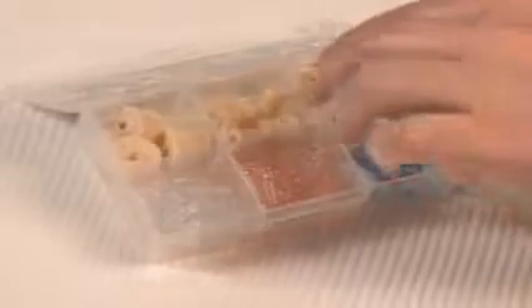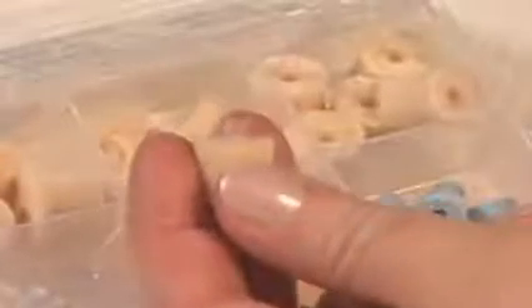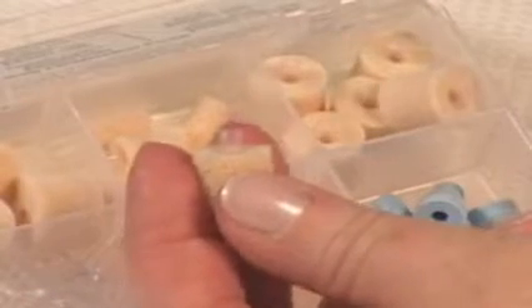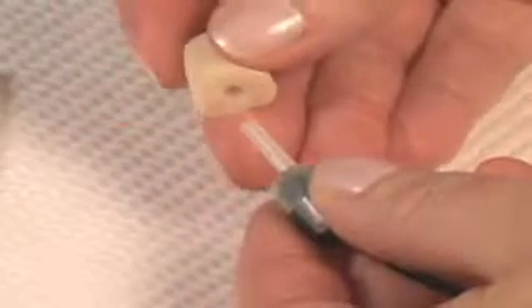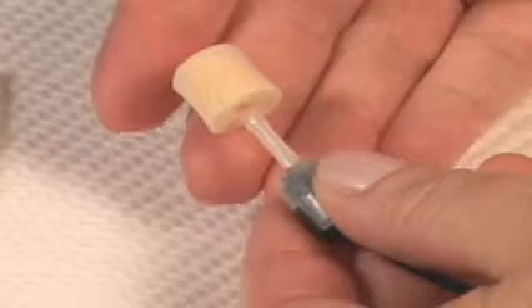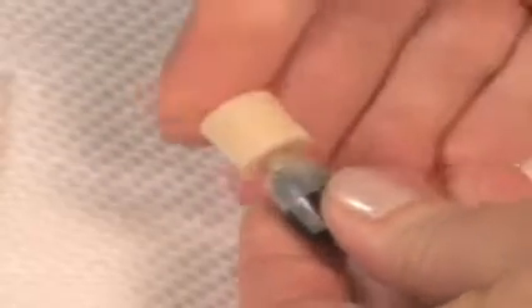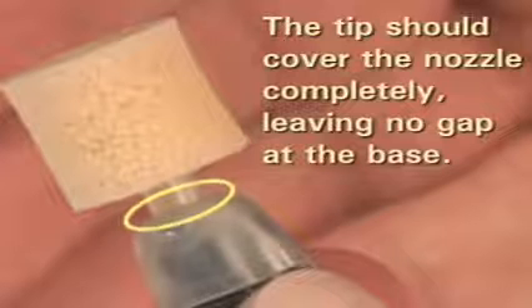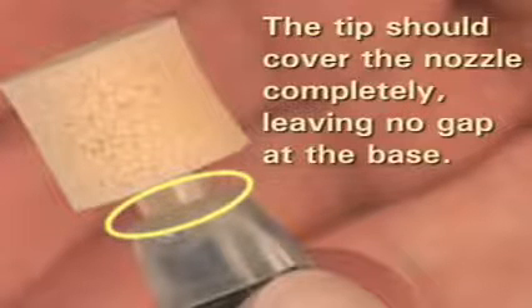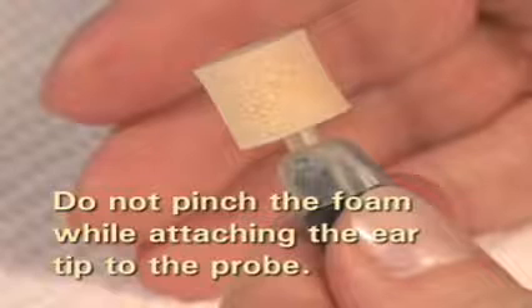For testing an older child or adult, use the beige foam ear tips. Select an ear tip that is a little larger than the patient's ear canal. Place the clear tube slightly onto the nozzle of the probe body. Then, using your fingertip, continue pushing on the top of the foam until the clear tube completely covers the entire nozzle with no gap at the base. Do not pinch the foam while attaching the ear tip, as this will make it harder to install the tip properly.